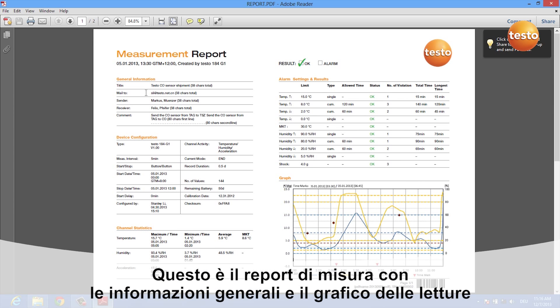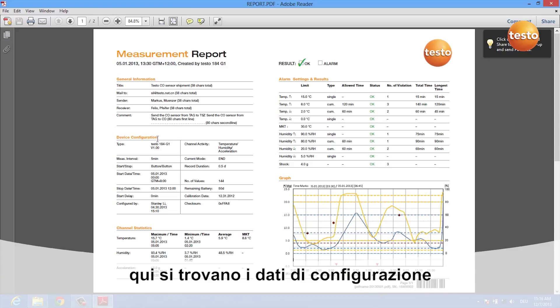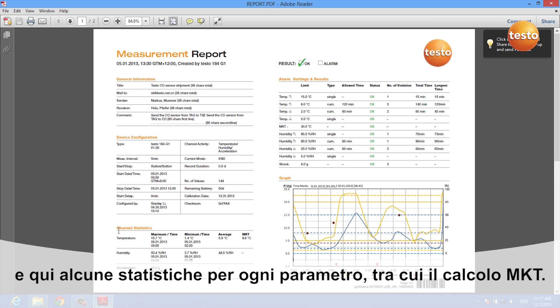Here you see the complete measurement report of your data logger and you get some general information about the device, you get information about the device's configuration and you get some statistics for each channel including MKT calculation.